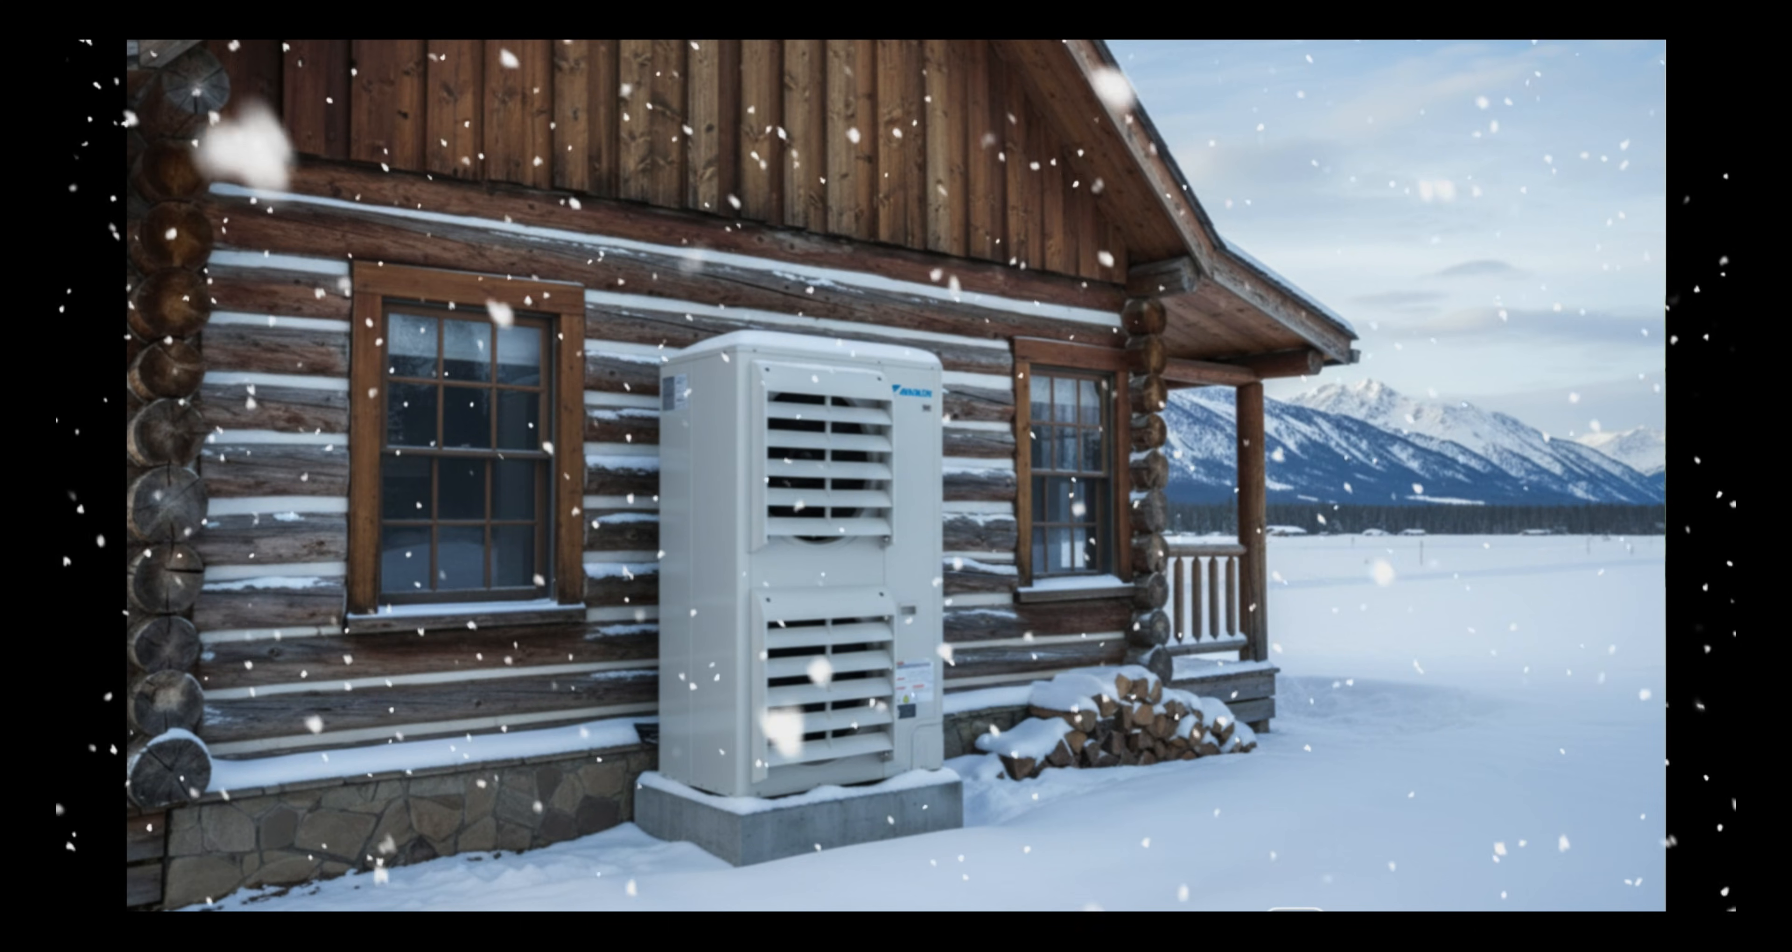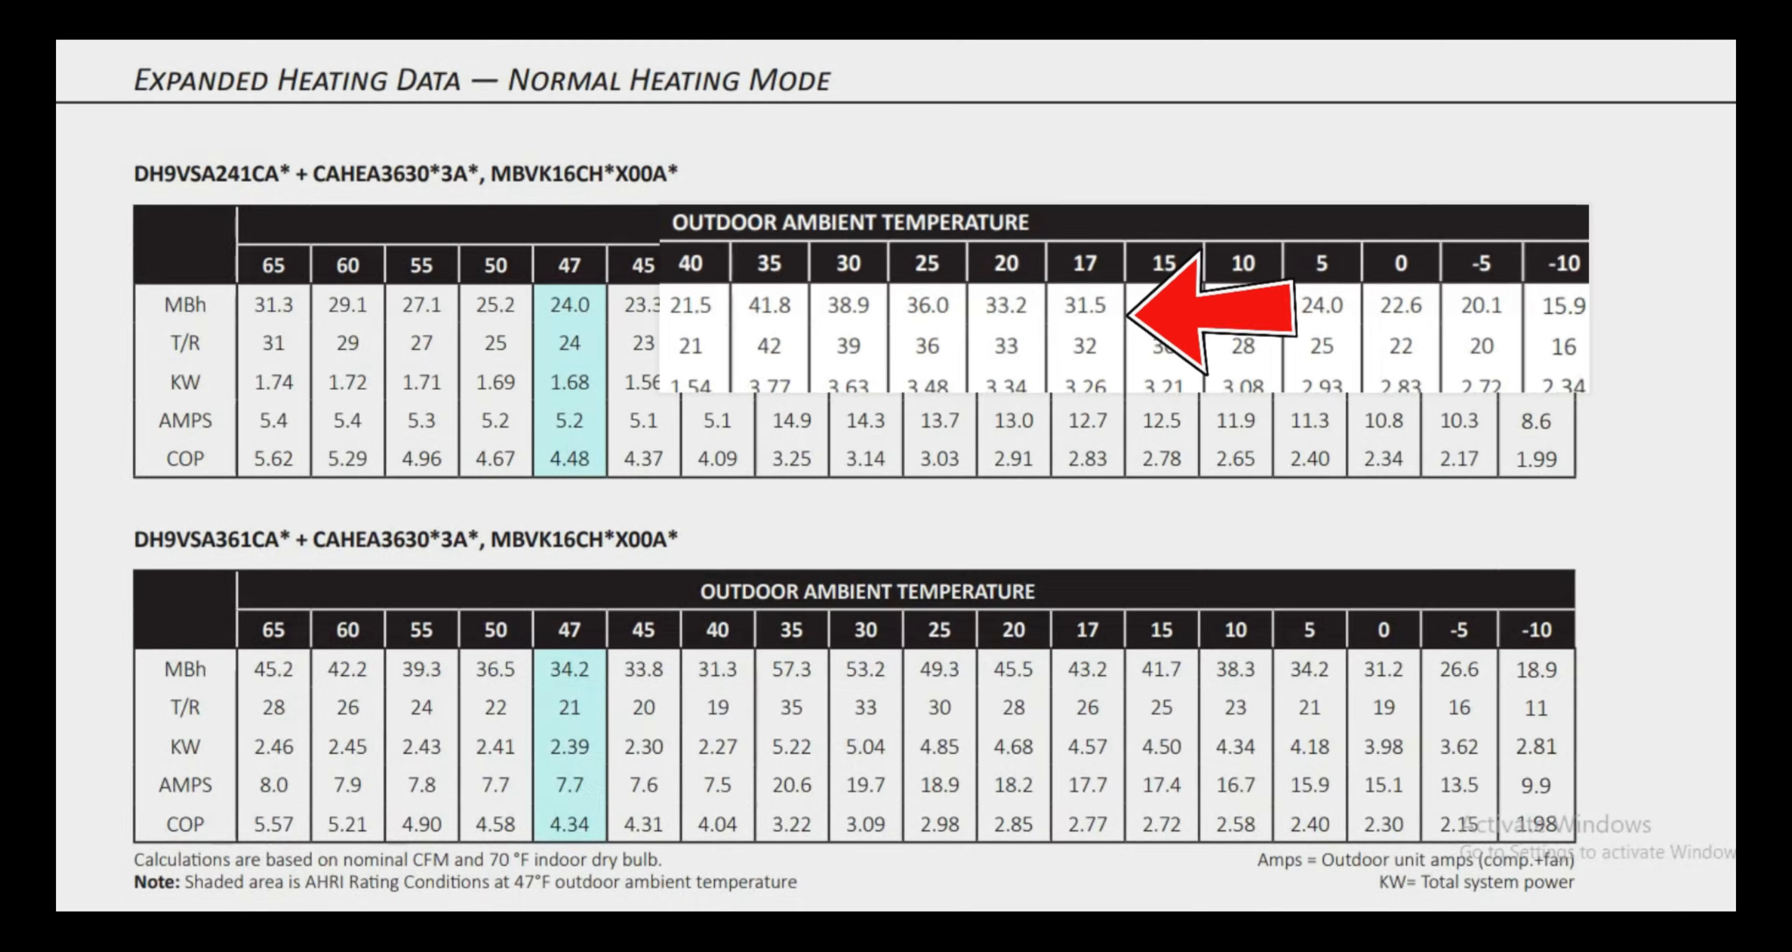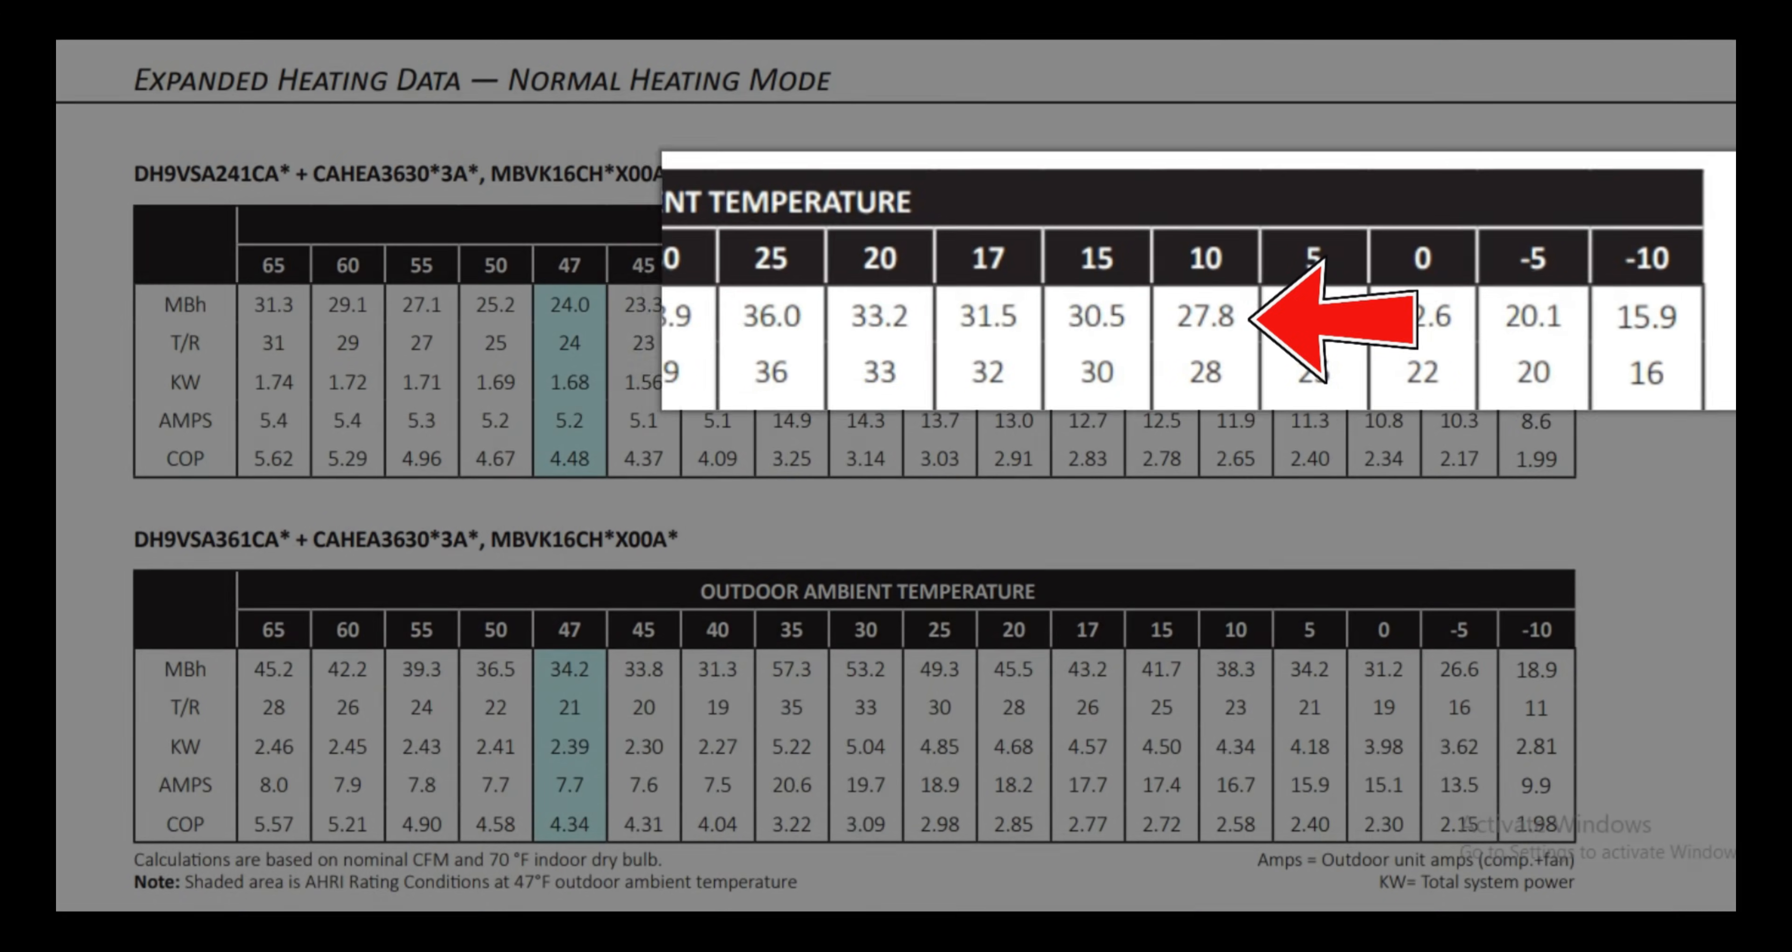As we get closer to freezing point at 35 degrees Fahrenheit, a two-ton Aurora becomes a three and a half ton heat pump, outputting 41,800 BTUs. At 30 degrees, we're still over three ton. At 25 degrees, we are exactly at three ton. At 17 degrees, we're still over two and a half ton, while the other system is running at nearly one ton capacity. At 10 degrees, we're still over two tons.